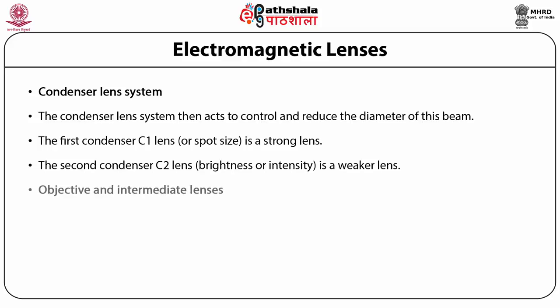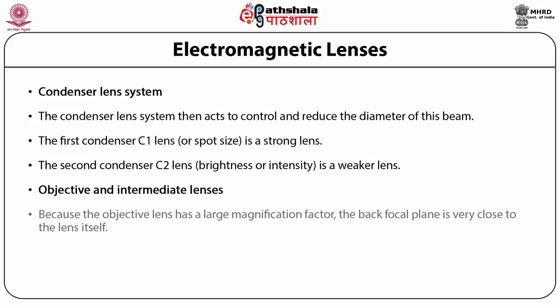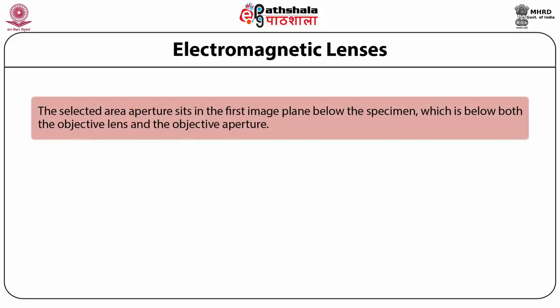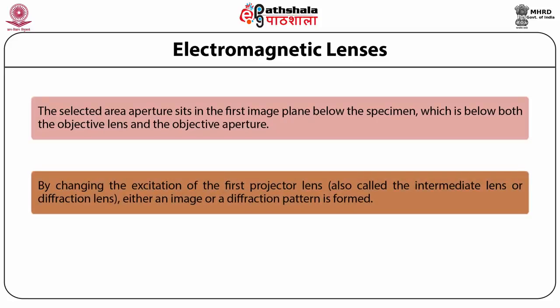The objective lens has a large magnification factor, which is why the back focal plane is very close to the lens itself. The objective aperture — the middle aperture on the column — is mounted in the back focal plane. Inside the first image plane beneath the sample, a selected area aperture is placed underneath both the objective lens and the objective aperture. By altering the first projector lens excitation, also known as the intermediate or diffraction lens, either an image or a diffraction pattern is produced.